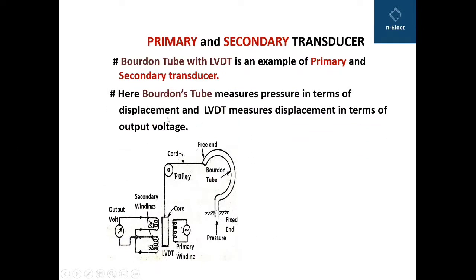The Bourdon tube measures pressure in terms of displacement. When pressure is applied to its fixed end, the free end of the Bourdon tube moves. The displacement of the free end takes place in this direction, and that displacement is a measure of pressure. So pressure is measured in terms of the displacement.